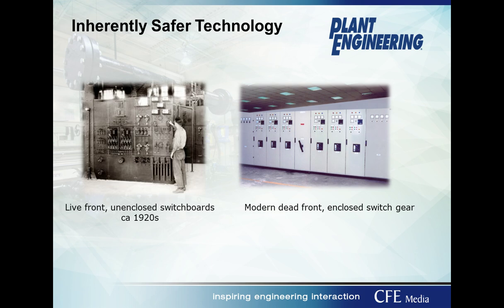I think this is the last pitfall I'm going to talk about, and I've got several slides on it: a failure to keep pace with the evolution of inherently safer technology. This first slide is a rather extreme example. In the photograph on the left, we see a live front, unenclosed switchboard, which was common and standard at least through the 1920s—some were installed even later in the U.S. and other parts of the world. We see a worker standing in front of it, and that worker's safety depends on knowing what not to touch on the front of that panel board, because there are live conductors, switches, fuse blocks, and terminals on that switchboard.